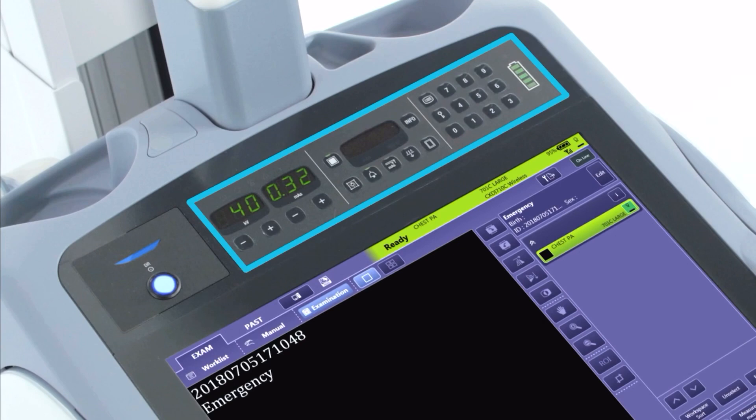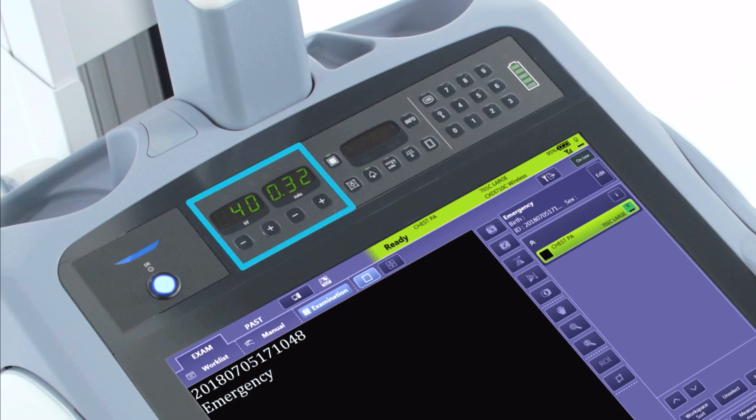Above the screen, you will find the unit's control panel. There, you can read the battery strength on the top right side and access the radiographic selections and LED collimator button switch.